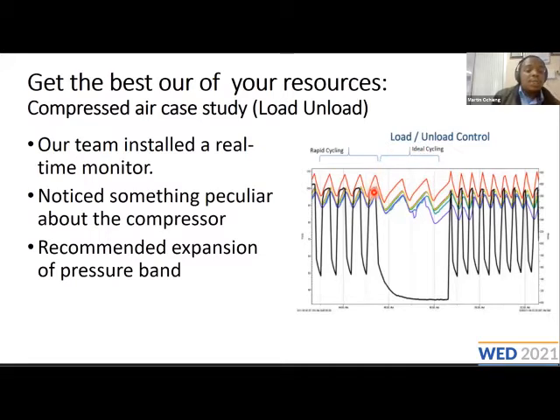Basically, once it loads to the end, it should be able to unload and take a little bit longer on the unload cycle. But in this case, as you can see on the first section here, there was rapid cycling of that particular compressor, and we were able to identify maybe what the problem was. The problem was that the pressure band for that particular compressor's operation was a little bit narrow.